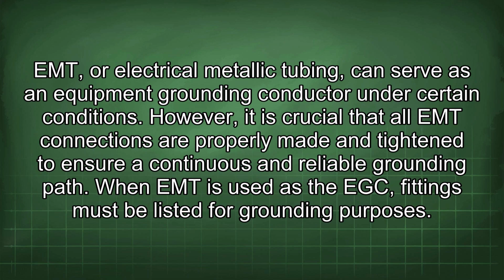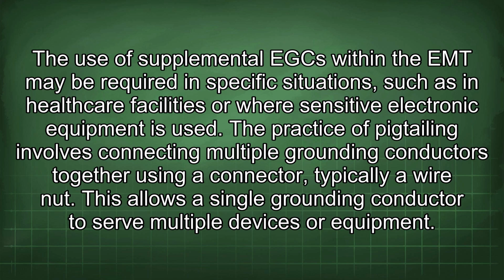EMT, or electrical metallic tubing, can serve as an equipment grounding conductor under certain conditions. However, it is crucial that all EMT connections are properly made and tightened to ensure a continuous and reliable grounding path. When EMT is used as the EGC, fittings must be listed for grounding purposes. The use of a supplemental EGC within the EMT may be required in specific situations, such as in healthcare facilities or where sensitive electronic equipment is used.